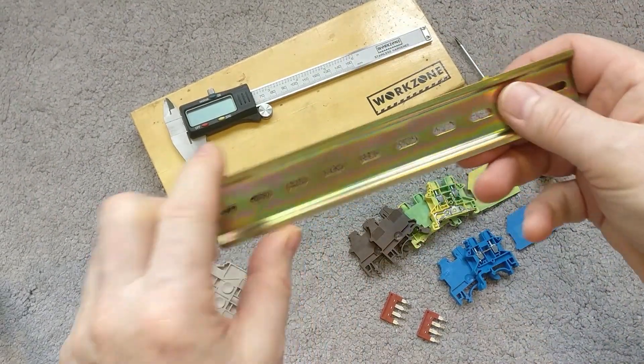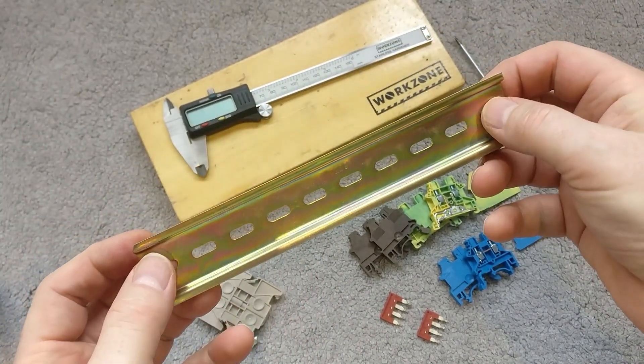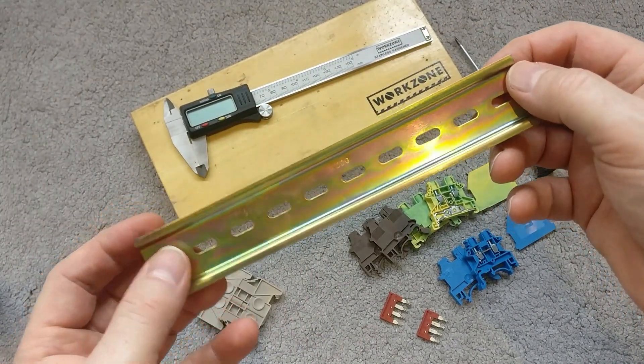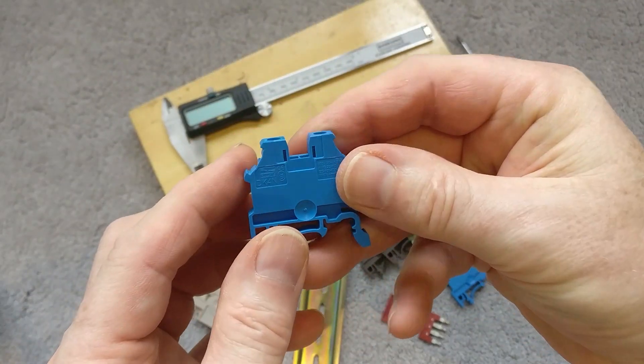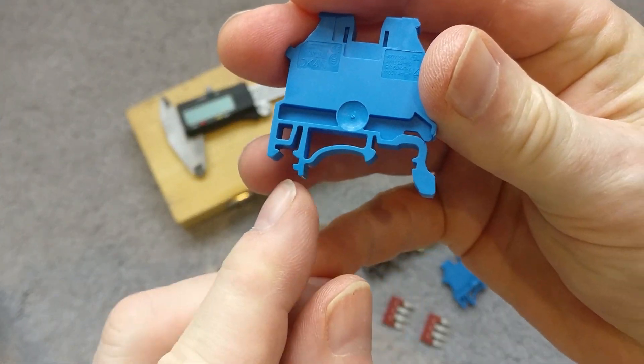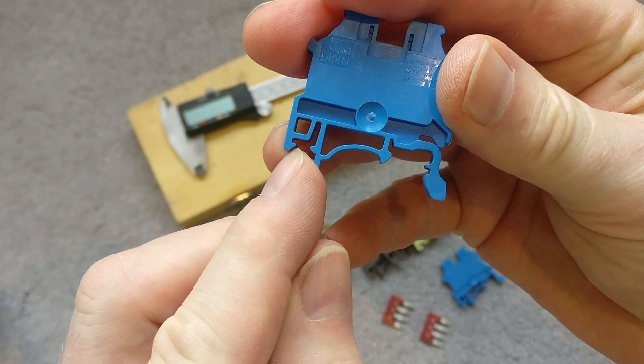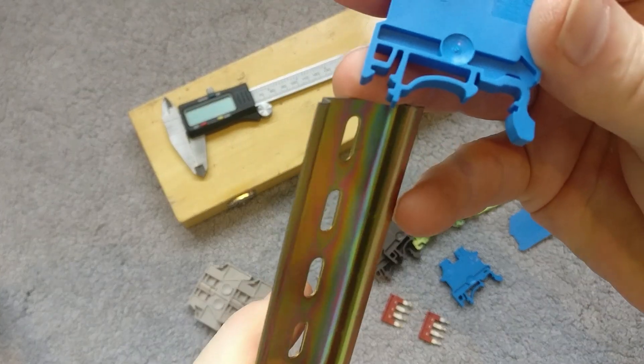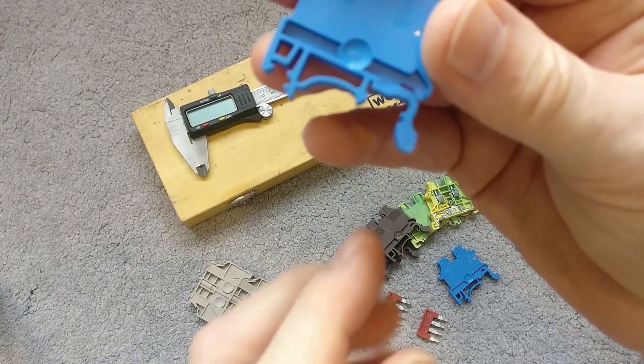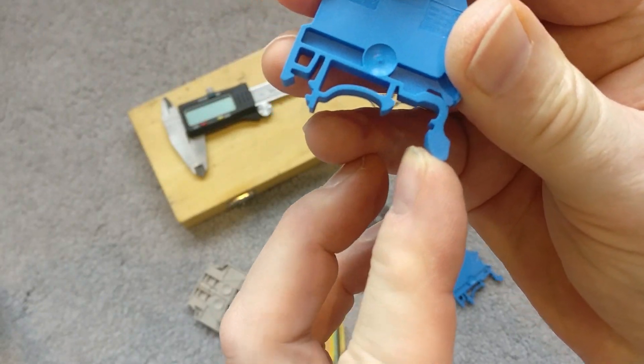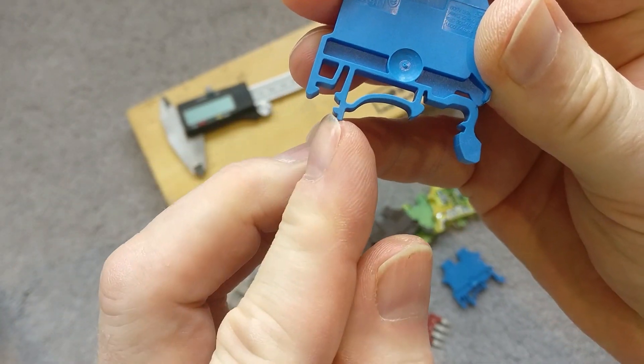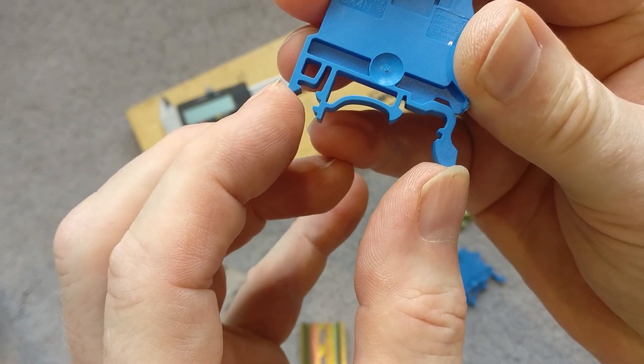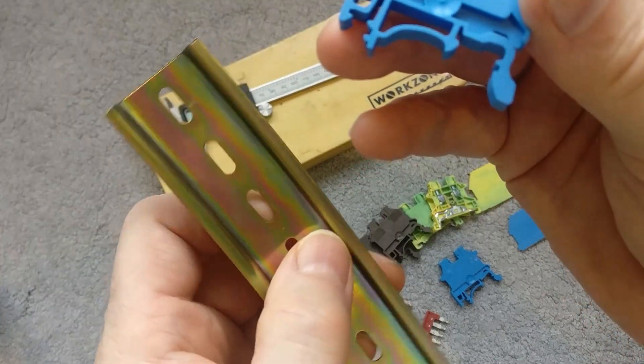First of all, let's look at how they connect to a DIN rail. This is a standard 35mm DIN rail. You've got these little recesses which clip over this lip on the DIN rail, and then the plastic by its nature is quite springy, so this piece actually pushes down on the DIN rail and makes sure that these two are pushed out and clamped in tightly.